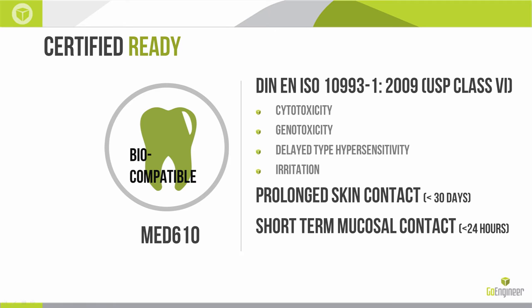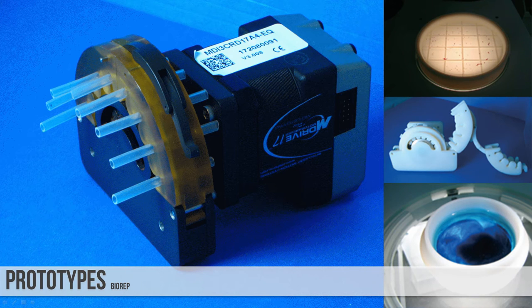Cytotoxicity means being toxic to cells, like venom — this material won't poison your cells. Genotoxicity refers to chemicals that damage or mutate cells — not a concern here either. Delayed-type hypersensitivity means handling the material and reacting two to three days later — no problem. And for irritation, you won't see inflammation as long as you stick within the prescribed time limits: prolonged skin contact under 30 days, and short-term mucosal contact under 24 hours. MED-610 is rated for all of these, which is impressive for a 3D printed material.